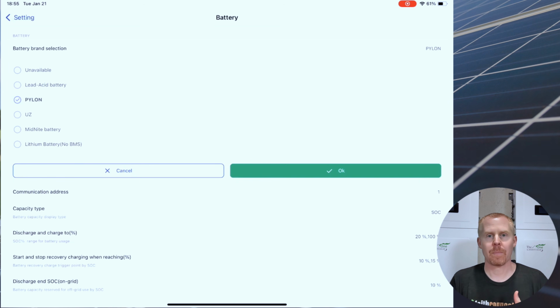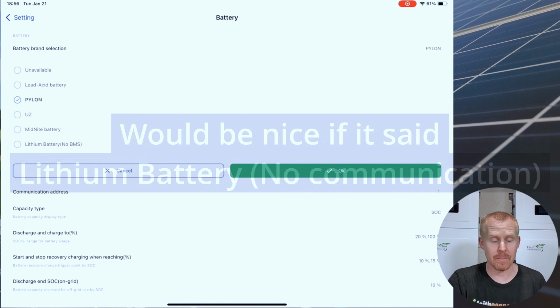So some inverters, you either set them up with battery communication or you set it up to lead acid mode. You might have a lithium battery, but just a battery that doesn't have BMS communication. And in those instances, you would end up using lead acid mode. But in this inverter, they give you a lithium option that can be used with no communications. It's just called lithium battery, no BMS.